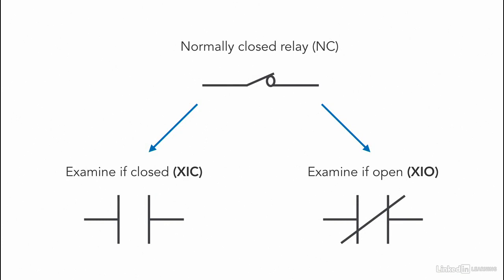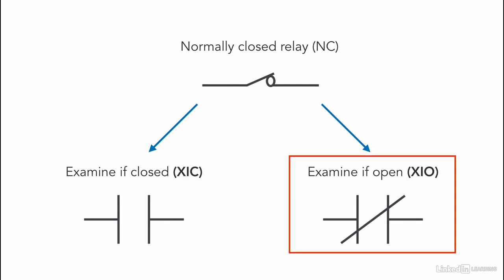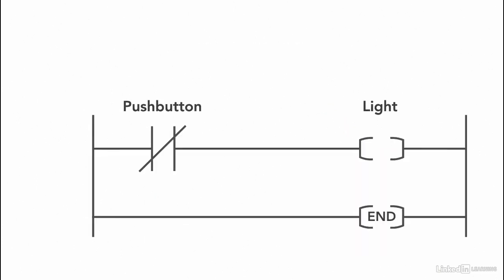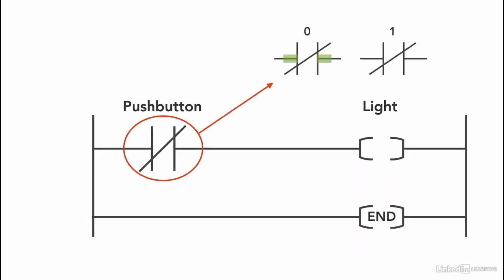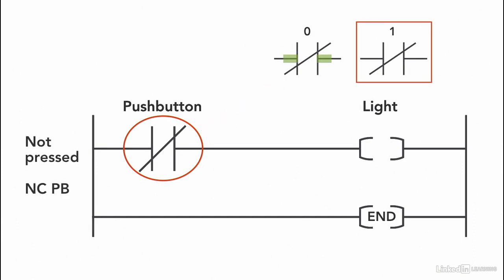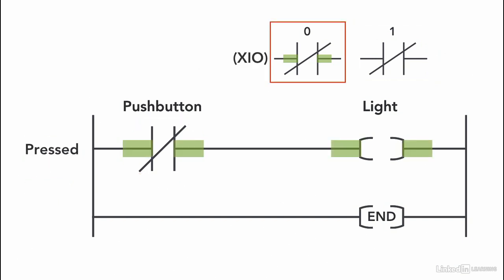Now, using the same physical device — a normally closed relay — with the examine if open (XIO) instruction. XIO is activated when the memory location is 0. So if the push button is not pressed, the memory location is 1 because we're using a normally closed relay. As a result, the XIO instruction will not be highlighted and the light will not turn on. Once the push button is pressed, the memory changes to 0, XIO is activated, and the light will turn on.